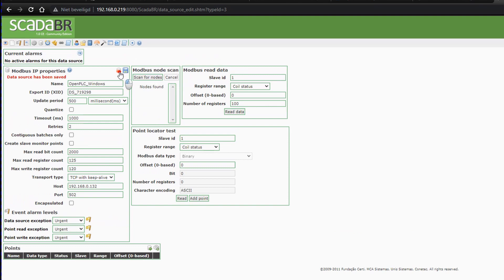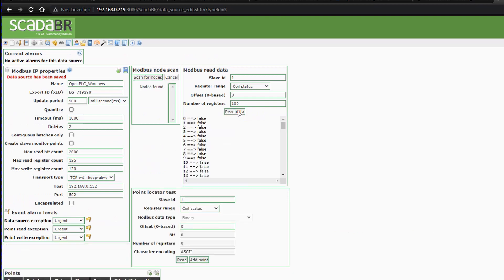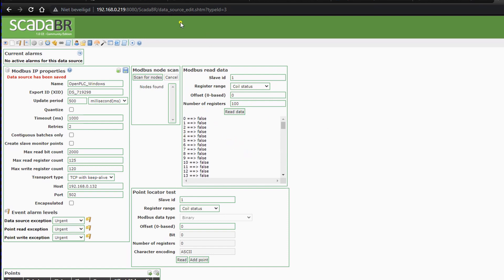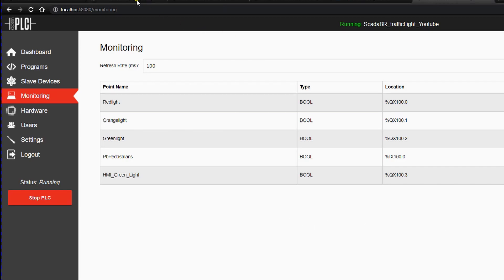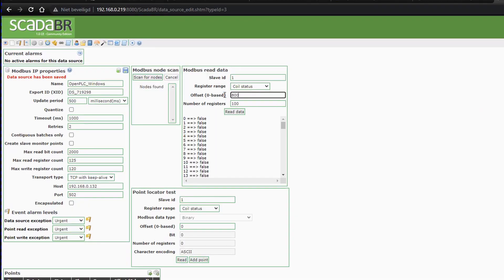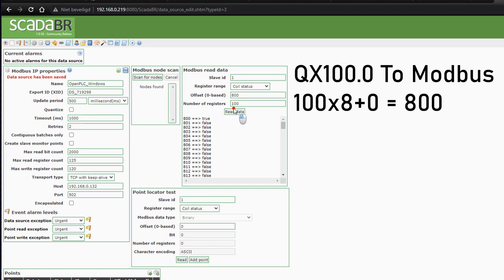If you have a connection and do Read Data, you will find these addresses. For addressing, you can use the Modbus slave addressing or you can use this formula: take the byte address, multiply it by 8, and add the bit address to the previous sum. So in this case the address is 100.0, meaning 100 times 8 plus 0 equals address 800.